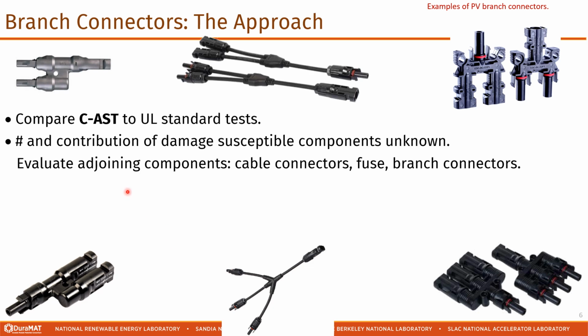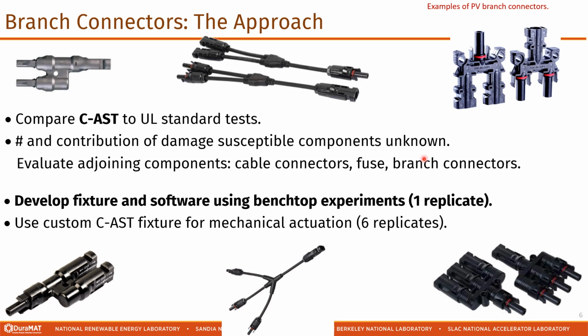So the approach here, I'm going to talk about today, is setting up to examine using CAST. Mike Kempe's working to examine relative to the UL standards. When we started, the number and contribution of the components in the system was not known. So we examined all of the adjoining components in CAST, including the cable connectors, discrete fuses, and branch connectors. And I'll show examples of developing the fixture and data acquisition software for benchtop experiments, where typically we're working with a sample at a time. And that will be evaluated in CAST instead, something like 6 replicates at a time.